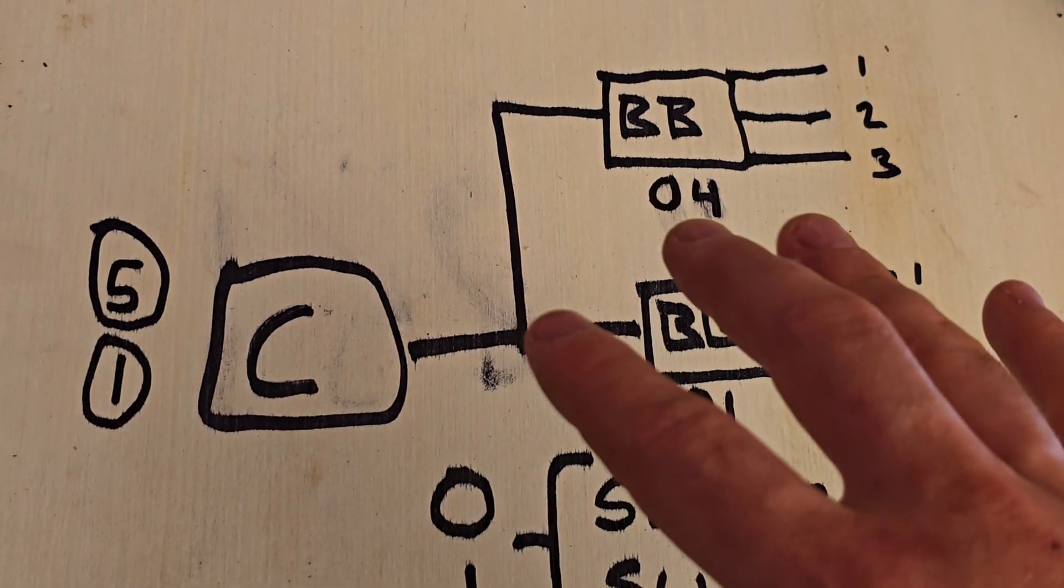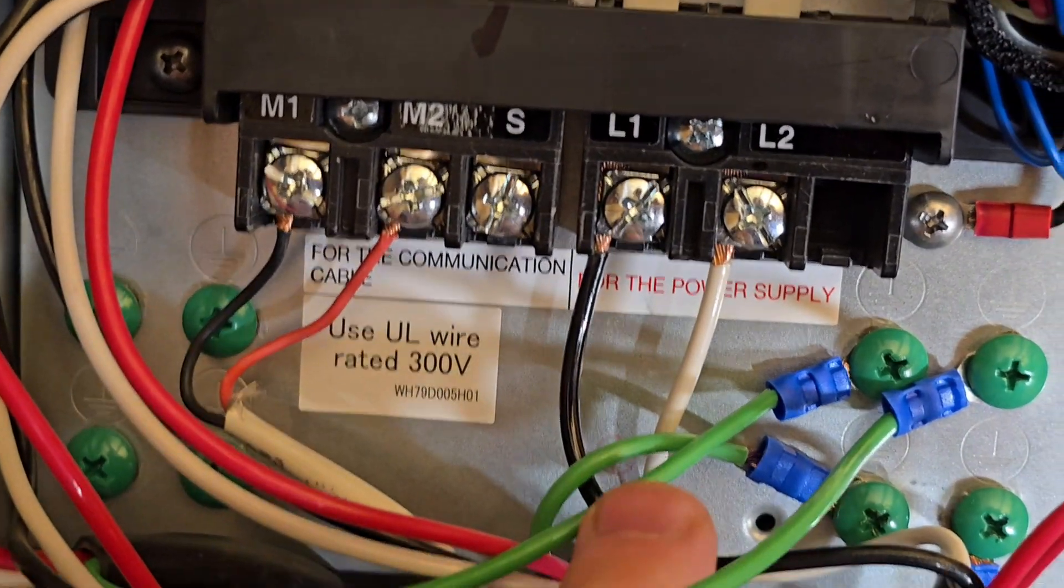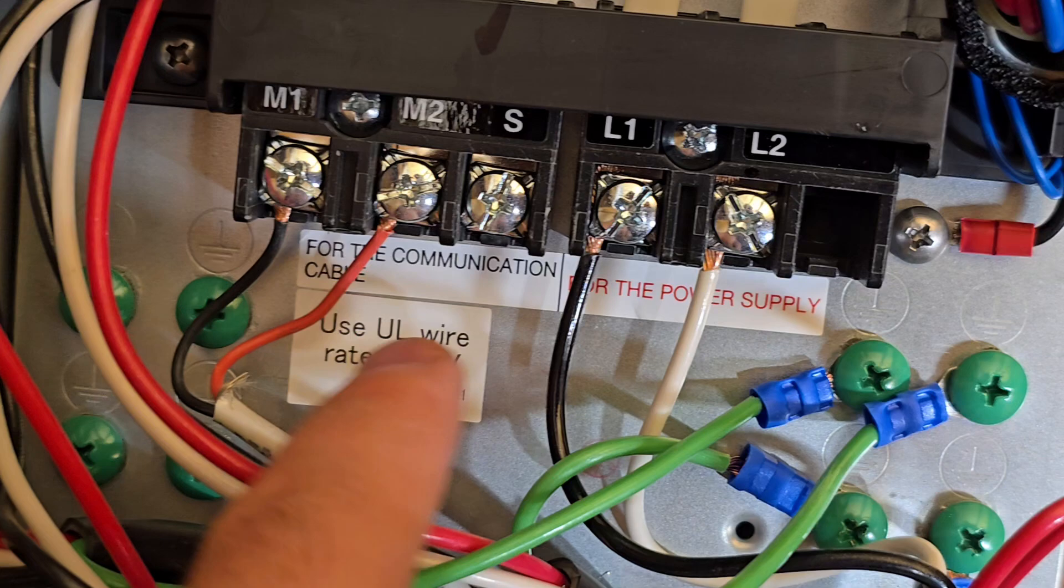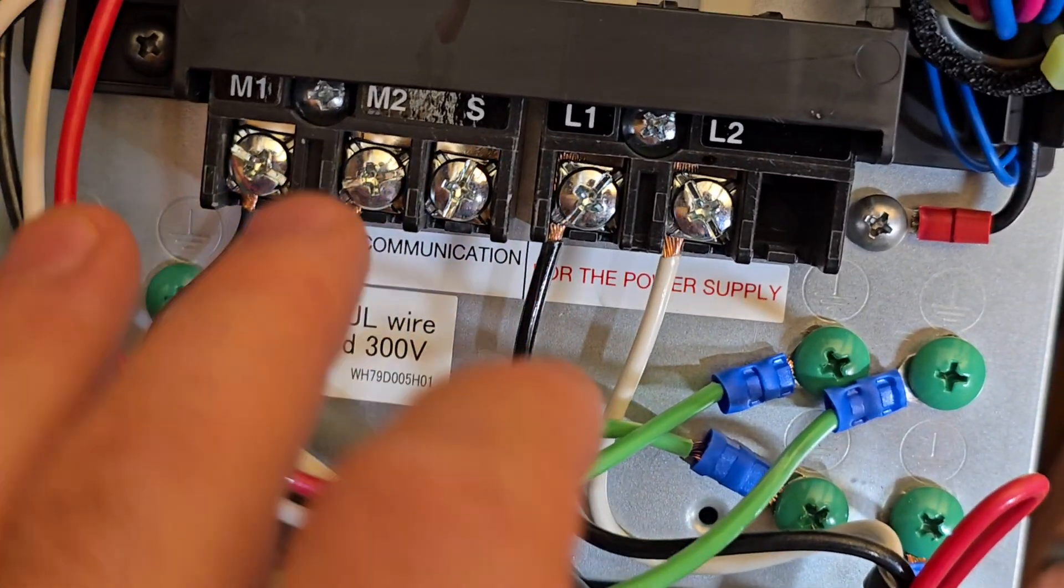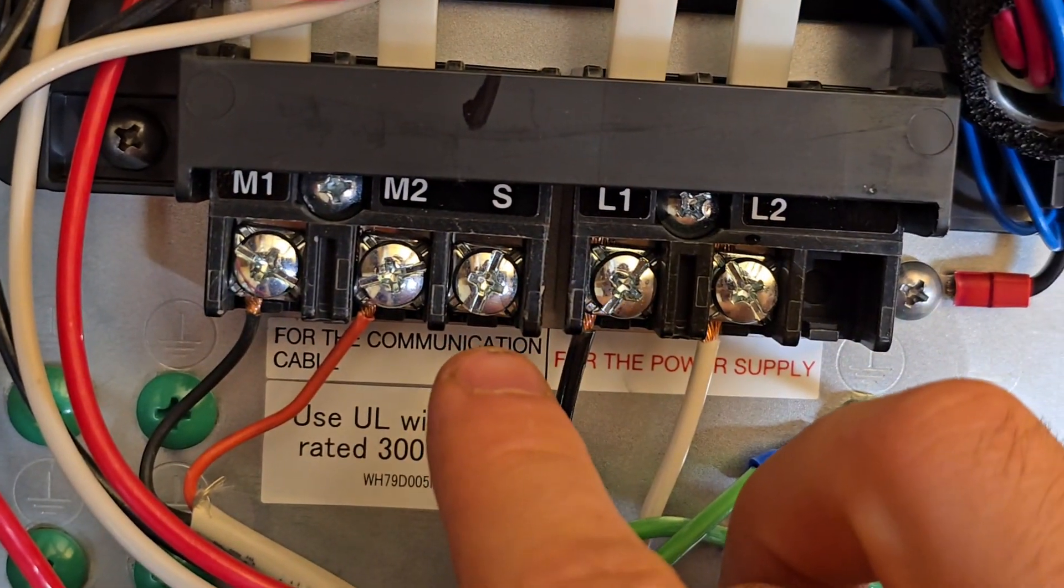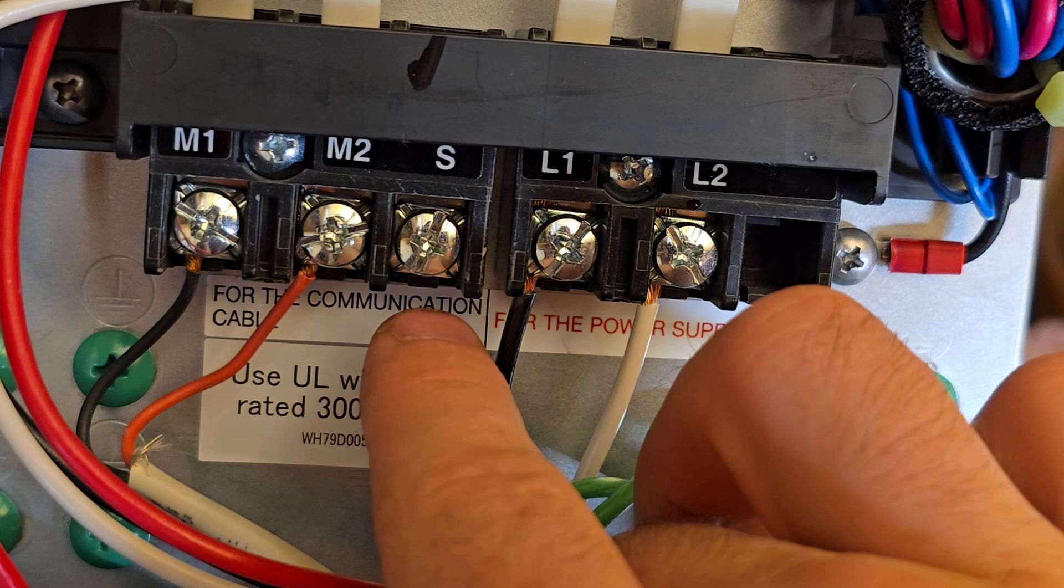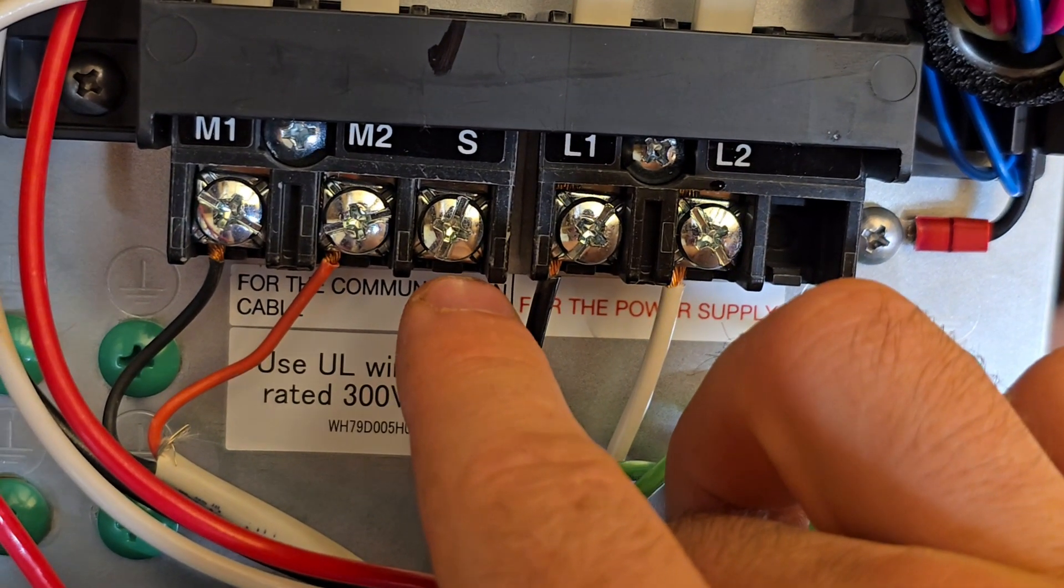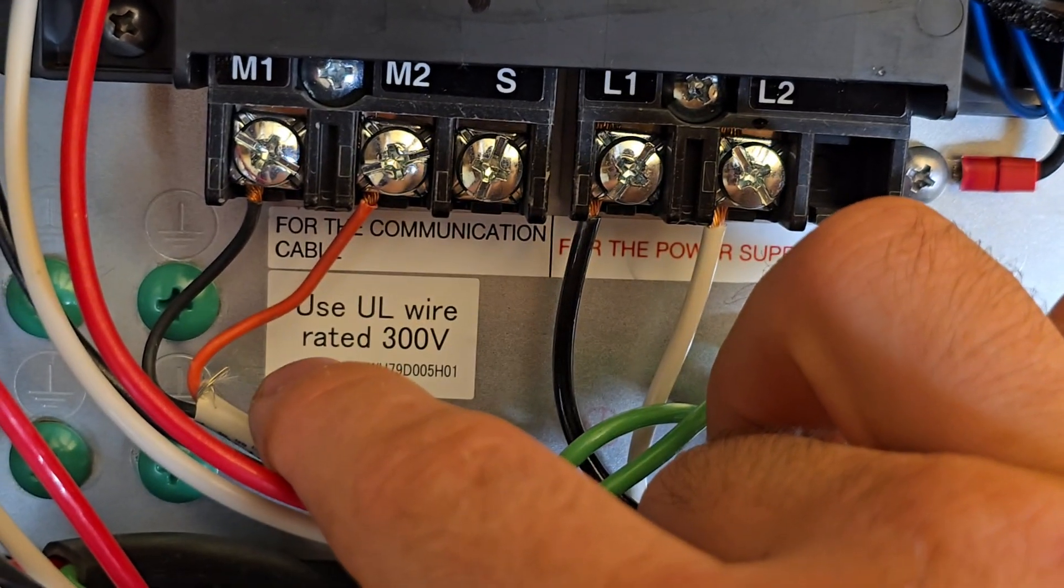All right, one last thing I wanted to mention. I've seen a couple people have these hooked up – this is your communications cable – and then you have your shield hooked up to both ends, and that is wrong. What you should do is have your shield hooked up to either your compressor or your branch box, one or the other. If you hook them both up, what can happen is you create a ground feedback loop, and it basically acts like a large radio antenna and can cause some electrical interference.